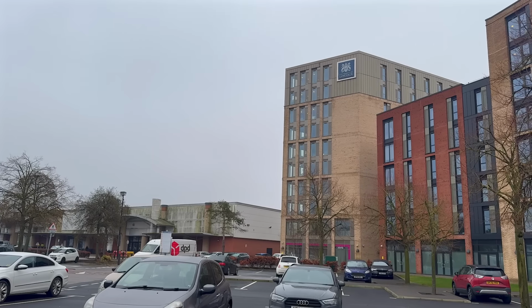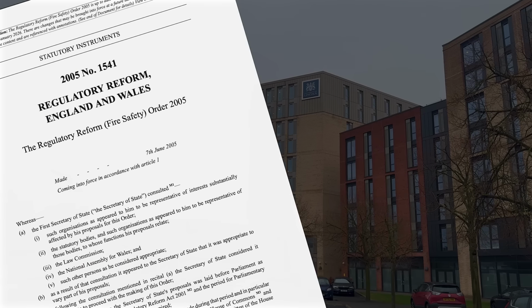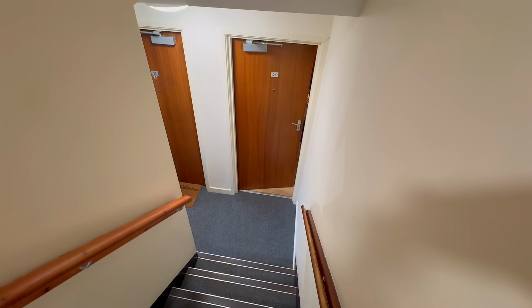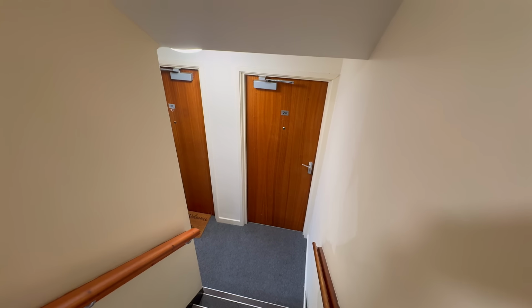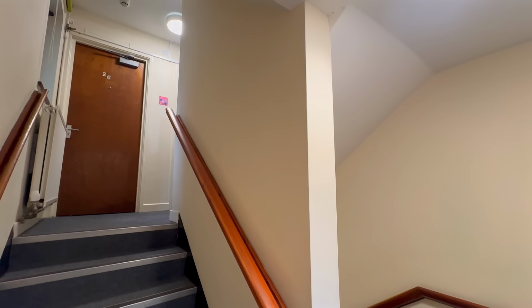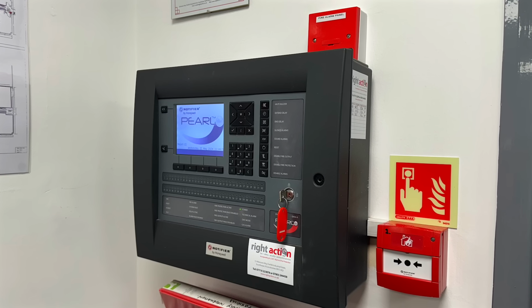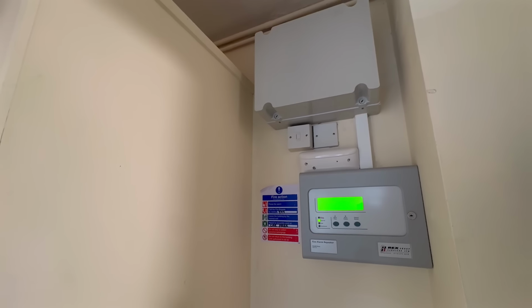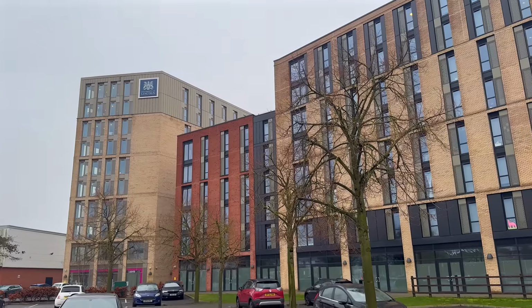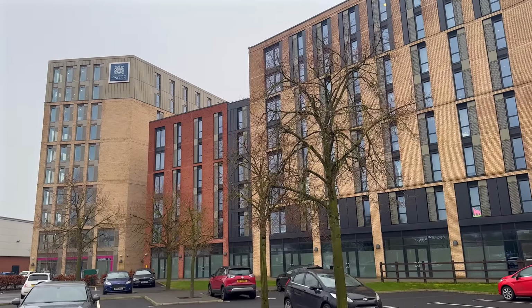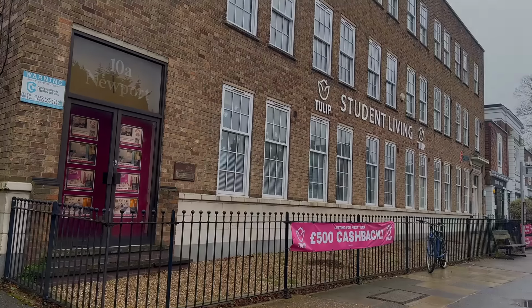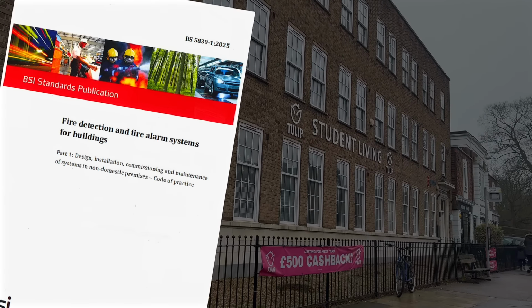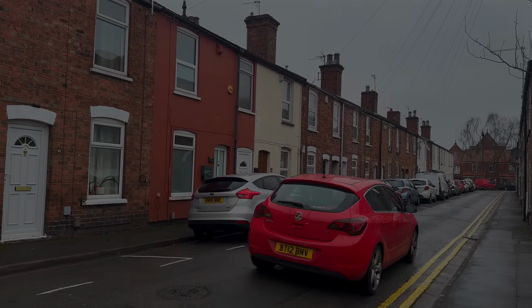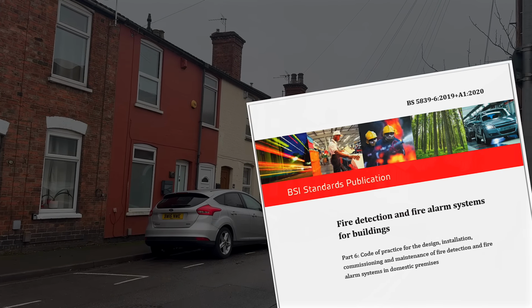Fire safety in these buildings is driven primarily by the Regulatory Reform Fire Safety Order. Under the Fire Safety Order, the responsible person has a duty to assess the fire risk and put appropriate fire precautions in place. That includes fire detection and alarm systems suitable for the size, layout and use of the building. In practice, this means purpose-built student accommodation is usually protected by a full fire alarm system designed to BS 5839-1 rather than the domestic fire detection systems under BS 5839-6. For electricians, the key point here is that this is not a domestic fire job, even though people live here.